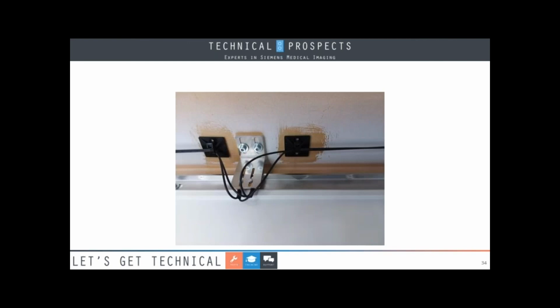One thing to keep in mind, and this is the same switch, only up close. You can see where you can adjust it, and there's that thin metal. That's the only thing it rests on. And you've got 8 switches there. So, yeah, but a safety switch will not keep you from making an X-ray. If you can get the components into the proper position, the operators can make an exam. These switches, however, can stop the operator from moving the overhead tube.